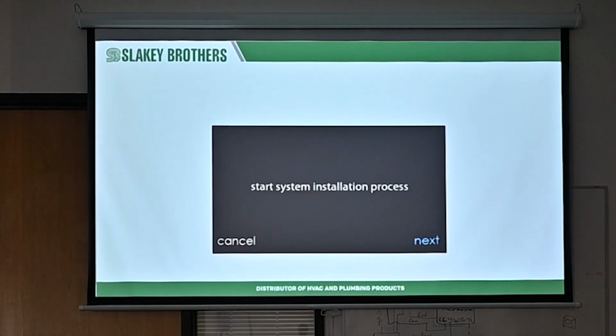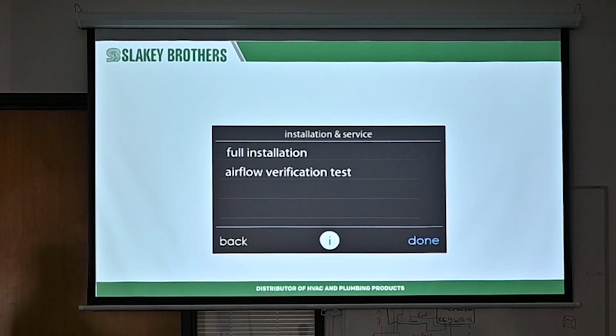Installation. All right. If you install a furnace, you commission it, you're all good to go. Now you're coming back in March or April and you're installing the condenser because they weren't ready for it, whatever it may be. You have to do a full reinstall. Because if you connect the condenser and then you go to air conditioning, it's not going to let you do anything. It's not going to register an air conditioner at all. It won't let you run air conditioning.